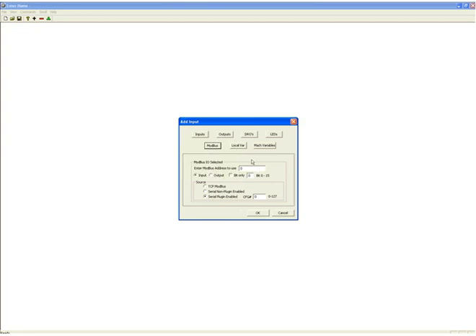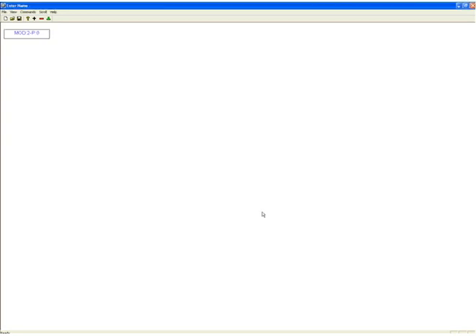not only do we set a Modbus address up here, and that number would be 0 to 127 for the data within that configuration group, but you set a configuration number.